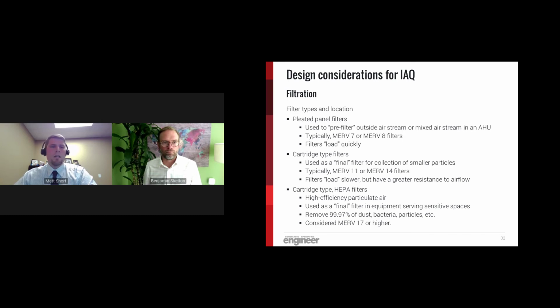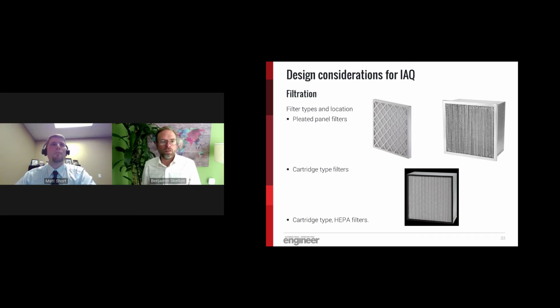And finally, to touch on cartridge type HEPA filters, HEPA stands for High Efficiency Particulate Air Filter. These are also commonly used as a final filter, most often in units that serve critical spaces such as operating rooms. These filters are capable of removing 99.97% of particulate matter, and they are technically considered a MERV 17 or higher filter rating. So Benny will now walk through some of those images of the filters we just discussed. Yeah, Matt, they can take lots of different shapes and sizes depending on the type of HVAC system you're going to be putting them in.